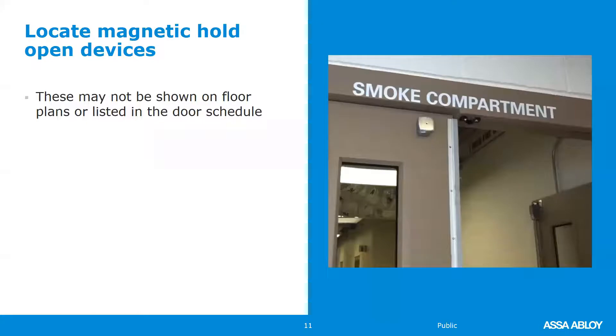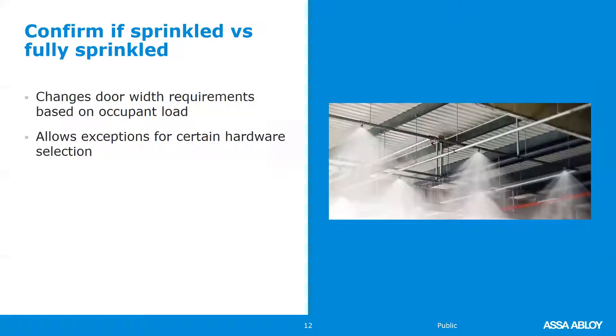The location of magnetic hold-open devices may not be shown on the door schedule, but they should be shown on the life safety plan — it could be a symbol, a note, or just initials. Additionally, confirm if the building is sprinklered or fully sprinklered or not: it changes your door width requirements based on the occupant load and also allows for exceptions for certain hardware selection, such as delayed egress and other special locking arrangements.